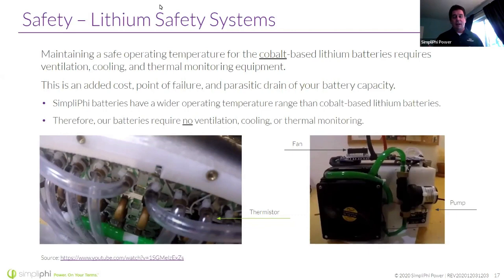A battery may have a heating and cooling system, right? That's great—it keeps the battery from getting too hot or too cold, but those are all uses of energy, so your battery has a drain on it from controlling the temperature range. Because SimpliPhi batteries have that wider operating range, which we'll see on the next slide, we don't need all this equipment—no ventilation, cooling, or thermal monitoring. And if you're a solar person who's been doing MC4 connections and getting into energy storage, the last thing you need is figuring out how one of these thermistor and pump systems has malfunctioned. It's equipment you don't want to be messing with.